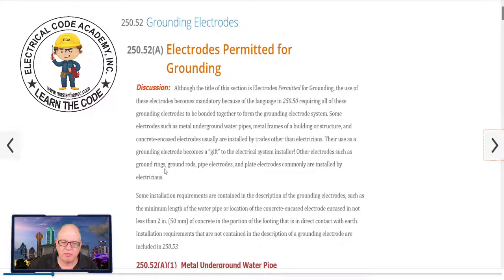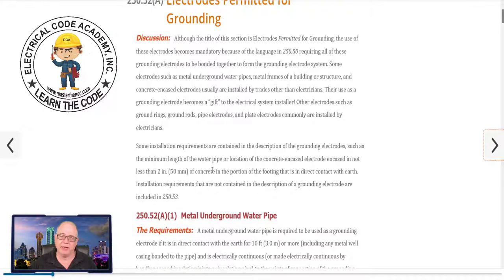Other electrodes — such as ground rings, ground rods, pipes, and plate electrodes — are commonly installed by the electrician, 100%. Used to be called man-made, but now we just say they're other than the big three inherent to construction — these are ones we have to install. As an electrician, I've got to go out and buy them and put them in. The most common by far is ground rods. Nobody wants to dig the trenches or lay a ground ring — at least in residential. In some big buildings like labs and hospitals, sometimes they will have rings with a more intricate grounding system. But for residential, we're not going through that. And if we're lucky, we have a Ufer ground we can utilize.